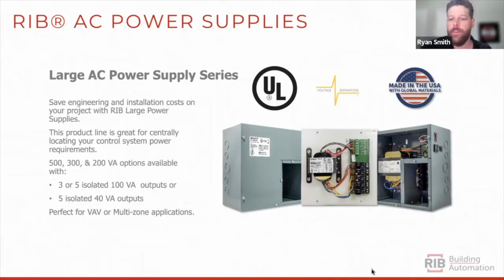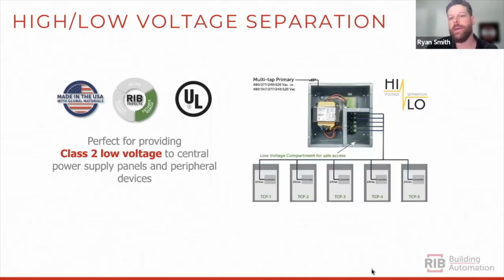This category features 500, 300, and 200 VA options with 5 or 3 isolated 100 VA outputs or 5 40 VA outputs. Large AC power supplies are great for locating all your power requirements for a project in a central location instead of placing transformers inside terminal boxes. This dramatically reduces installation time and makes troubleshooting a problem much easier. Features available include multi-tap primaries, power outlets, and a low voltage compartment that makes servicing the 24-volt AC connections and switches easier to access by not having to navigate your fingers around the primary voltage connections.